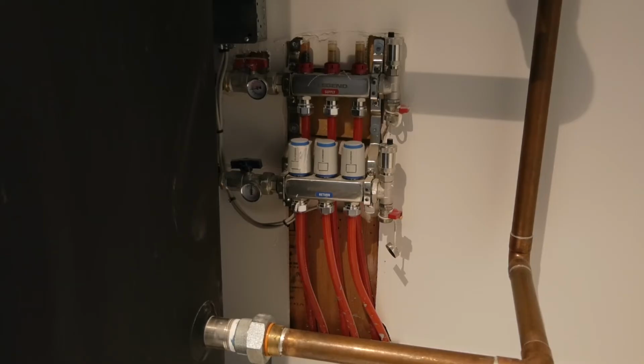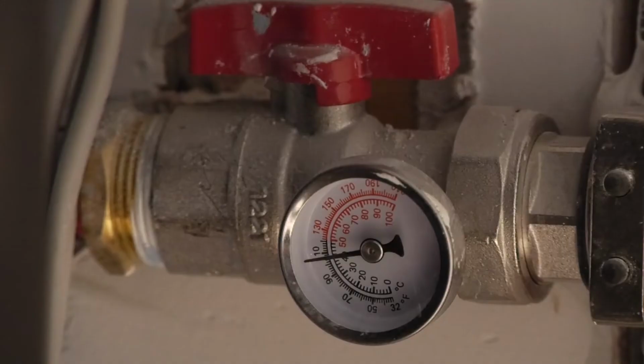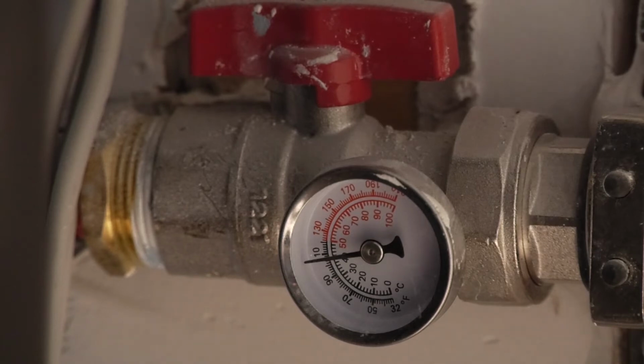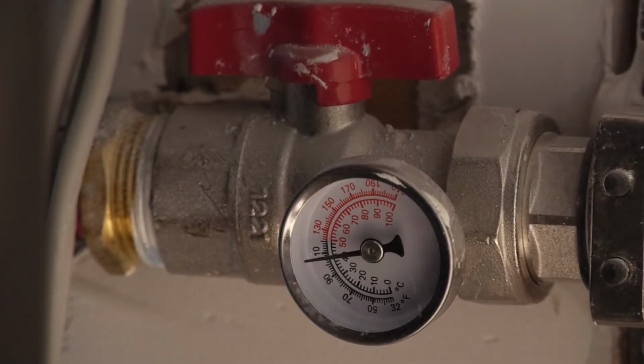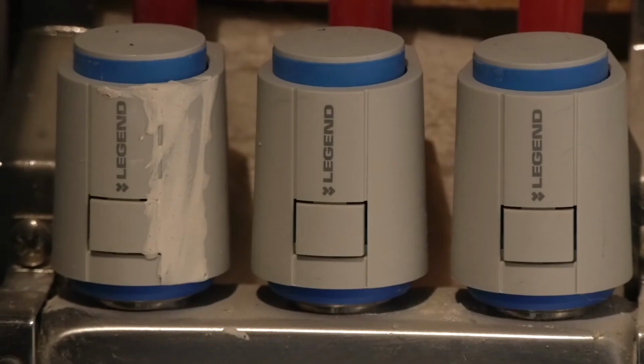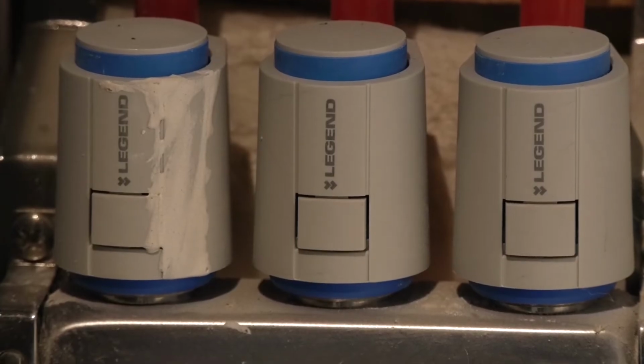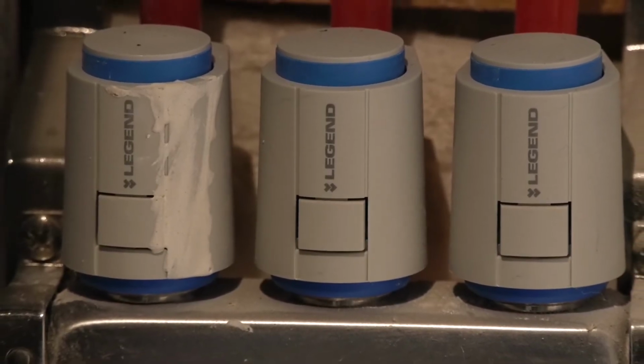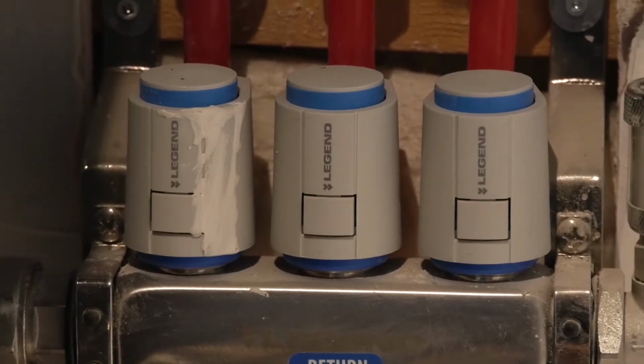We can still transfer the same amount of heat from one circuit to the other. High flow, low delta T meets low flow, high delta T. BTUs still transfer. So decoupling it, very important. 4-port buffer tank, very easy way to achieve hydraulic separation. So very popular for that reason.